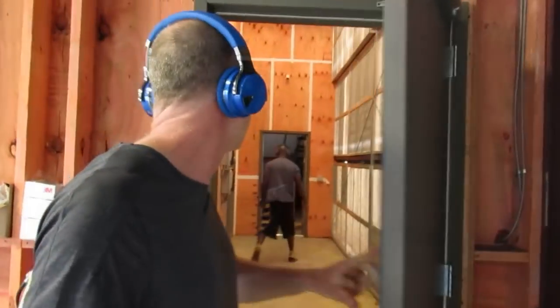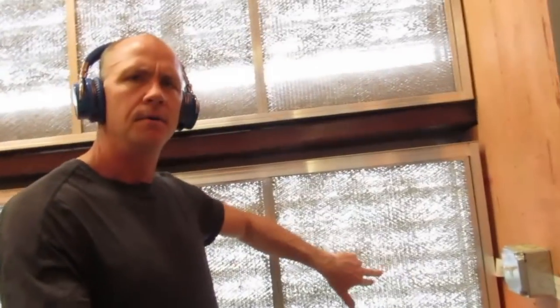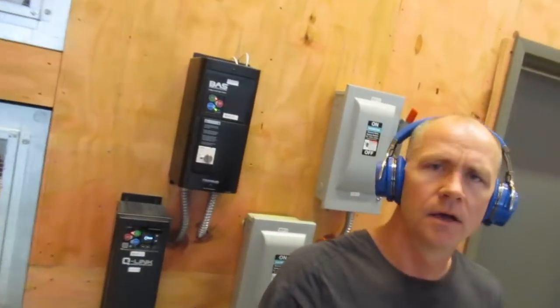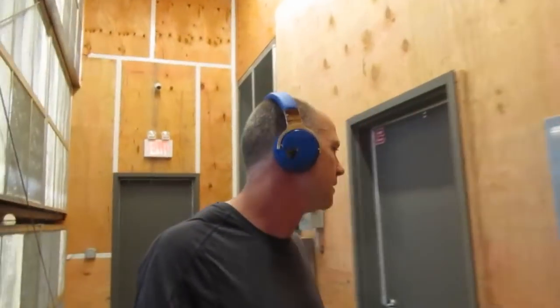So let's go into this first door here where you'll see the air intake and mixing room. So the air comes in from the outside, you saw the outside, and it goes through these vents and then filters. The filters are removable and can be washed and cleaned. They're made out of stainless steel. We have 4 of these fans, direct drive fans, that are 40,000 cubic feet per minute each, and I guess that adds up to 160,000 cubic feet per minute. So air comes in through the vents and filters, then goes into the mixing room, and then goes out through those 4 fans into the cold aisles.